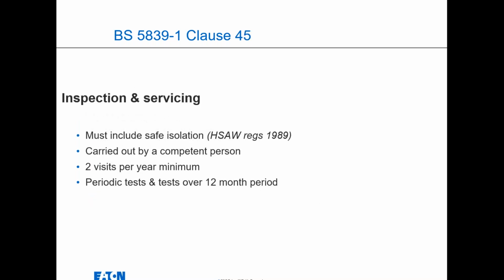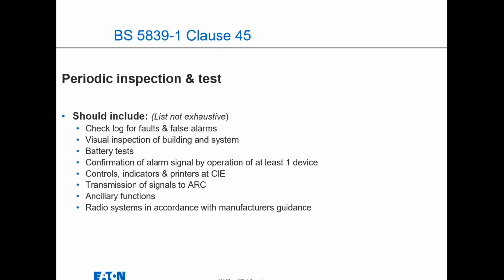So again, you should have inspections and servicing, 2 visits per year carried out by a competent person, and that should be periodic tests over the 12-month period. So pretty much everything should be tested. So that is a bit of an inspection and test logbook. Not exhaustive, but needs to be checked. And again, documentation should be part of the fire log as the end user's responsibility.